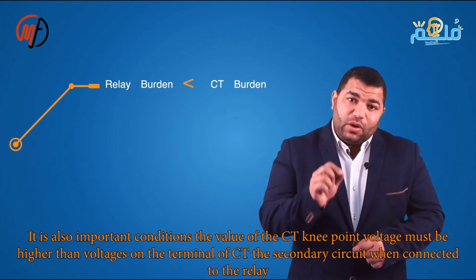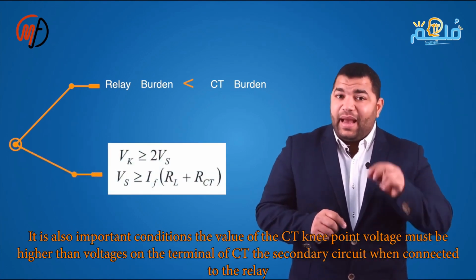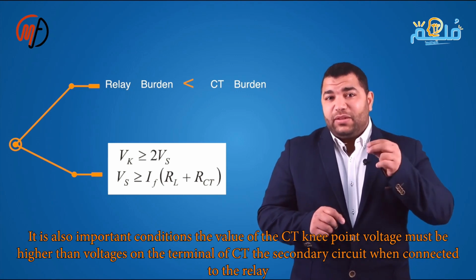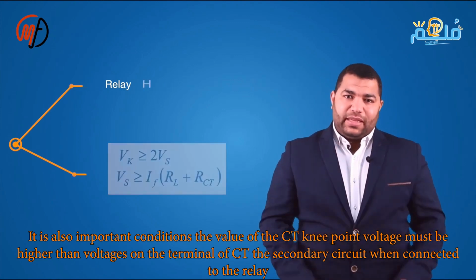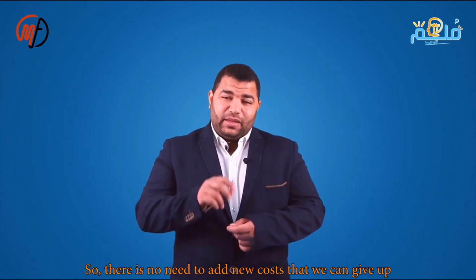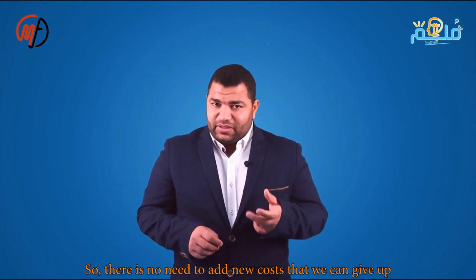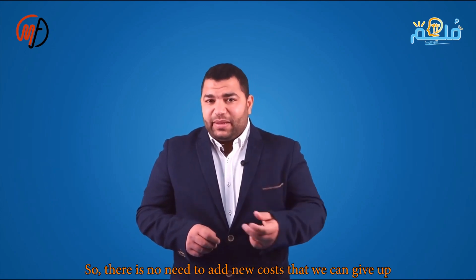CTs are for protection or measurement. Protection CTs have a higher knee point voltage than metering CTs to prevent quick saturation during a fault. Protection CTs operate over a wide current range, unlike metering CTs, which need accuracy within a limited range.